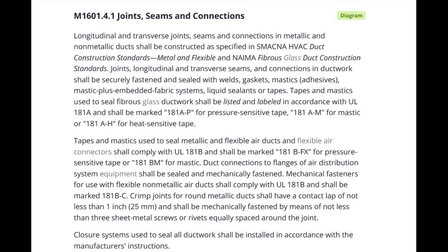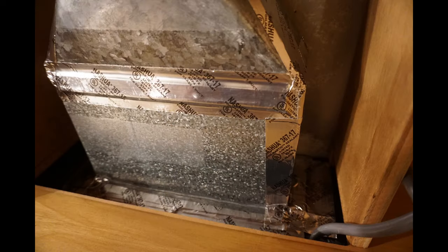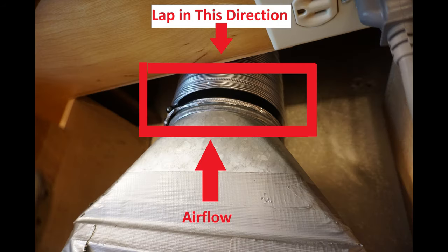Joints, seams, and connections must be securely fastened and sealed. Metallic ductwork can be sealed with UL181B-FX tape or UL181BM mastic. Round crimp joints need at least one inch of lap. Lap the joints in the direction of the airflow.